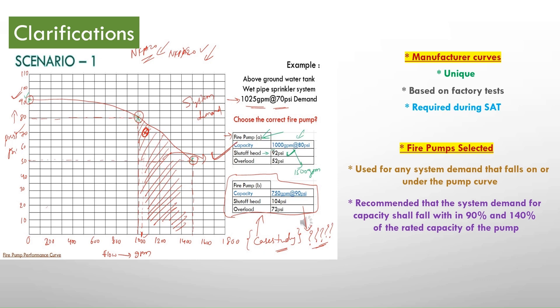However NFPA 20 recommends that the system demand for capacity shall fall within 90% and 140% of the rated capacity of the pump.